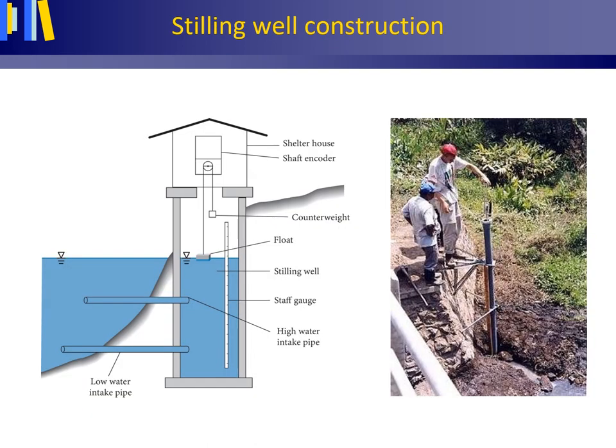A good way to continuously measure the water stage is a stilling well installation that is connected to a brook or small stream by water intake pipes. Such a setup has the advantage that oscillations due to the turbulence of the water flow are subdued. The photo to the right shows a similar setup where water levels are monitored in a small channel connected to the stream, also to subdue oscillations due to turbulence.